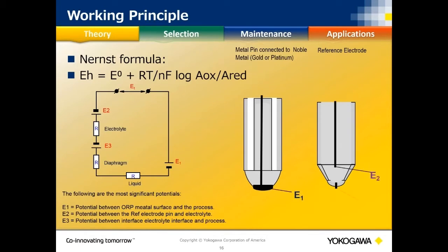In the electrical circuit, since we use the same standard reference electrode, the E2 and E3 voltage from the silver chloride pin in KCl and the junction open to the process — Nernst assigned that combination a zero millivolt potential. So the only voltage measured, E1, is generated by the ORP reaction against the noble metal, normally gold or platinum. If the junction gets plugged, a potential generates there and adds errors to your ORP measurement, just as with pH.